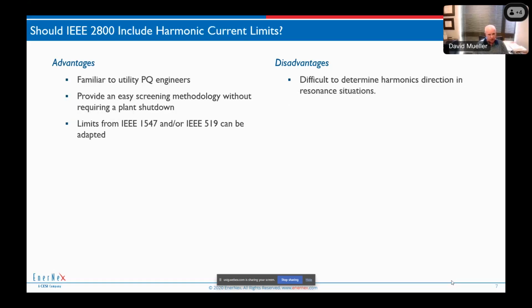On the other hand, harmonic current limits in theory are fairly easy to apply. I mean, you just go measure the harmonic currents. If we're below that, then we're good. That was a familiar concept to utility power quality engineers in the US who were familiar with the IEEE 519 harmonic standard, which is actually very popular around the world because it has current limits that are fairly easy to apply. And so it provides an easy screening. But there are problems with current limits.